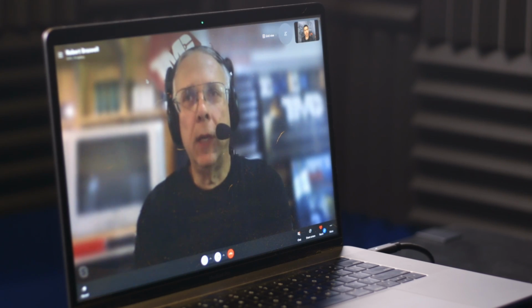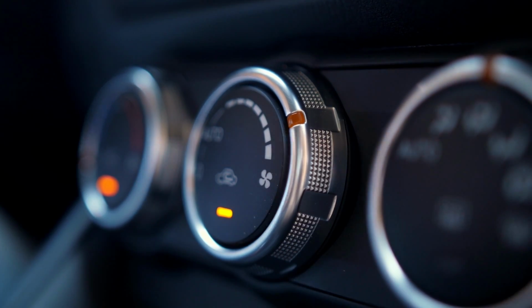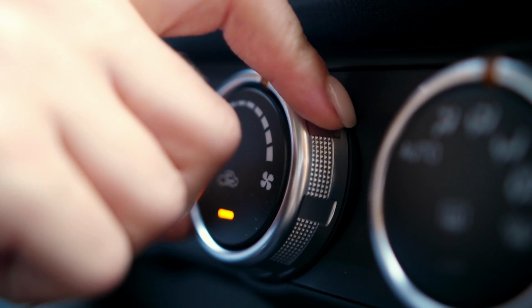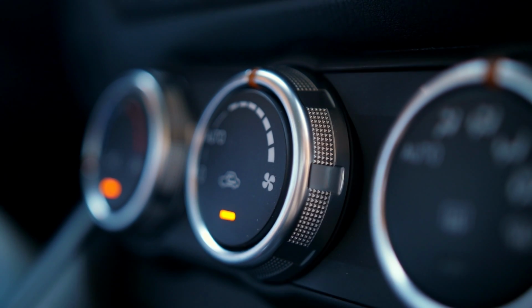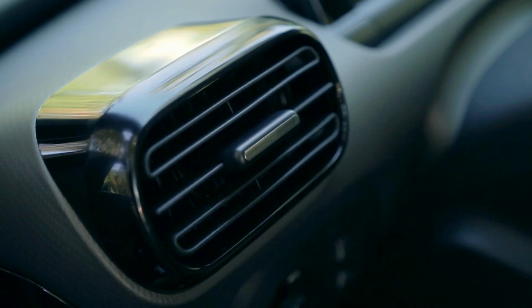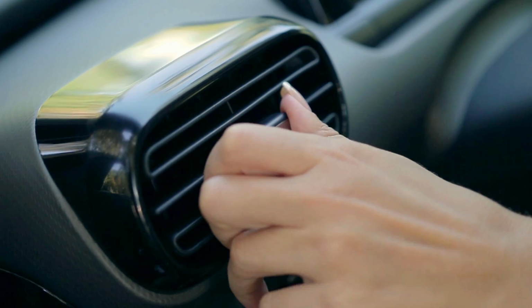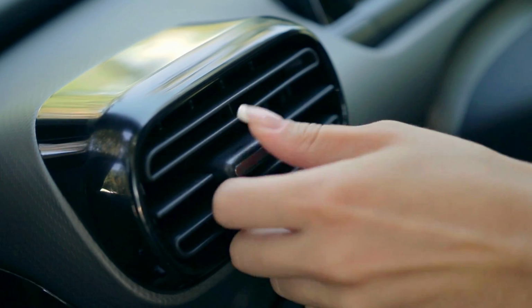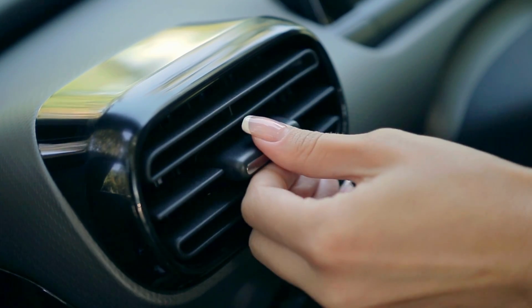Some folks will take either a digital or analog thermometer and put it in one of their ducts. Typically you'll see at the duct a temperature range of about 40 to 45 degrees Fahrenheit. If you have it on max cool and it's somewhere north of 55 or 60, it's not performing up to optimum spec.